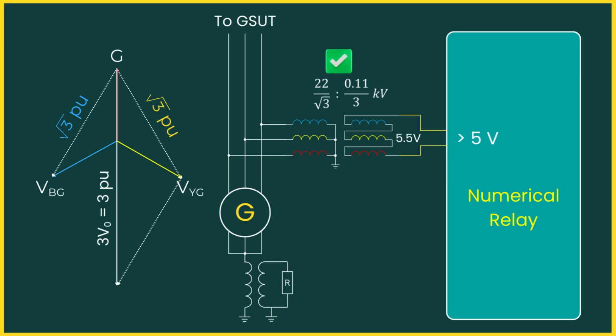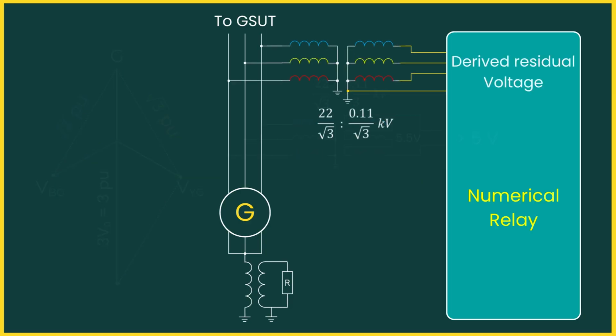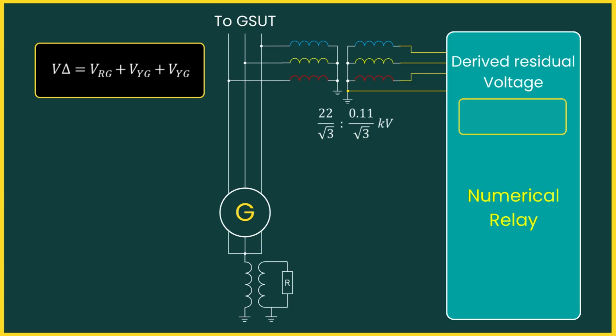Thus, the open delta method provides the same fault detection principle, but through phase VTs instead of a neutral grounding transformer. Now, let's look at the third method. Modern digital relays simplify things even further. In these relays, the residual voltage can be derived mathematically from the three-phase voltages using this equation. The resulting residual voltage behaves exactly like the open delta output, providing the same fault detection principle without requiring additional VTs or wiring. The maximum residual voltage during a terminal fault corresponds to 3 times the phase voltage. For a fault located 5% away from the neutral, the derived residual voltage is roughly 5.5 volts. Accordingly, the numerical relay is set to pick up around 5 volts, ensuring 95% coverage. This approach avoids additional VTs and wiring, offering a cleaner, more economical solution in digital protection systems.